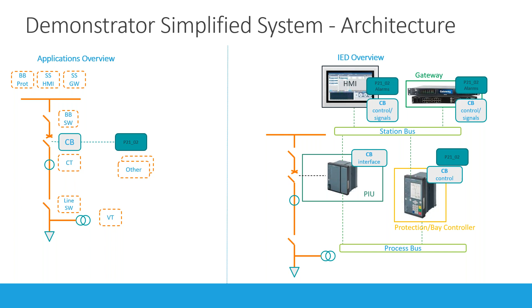The first device is a PIU, which holds the interface of the circuit breaker. The second is a protection or bay controller device, which controls the circuit breaker but also hosts the distance protection function. Then we have an HMI and a gateway: for the circuit breaker, they issue controls and manage positions; for the distance protection, they send or receive alarms, exchanging them with the bay controller or protection device. That's the system we're going to build.